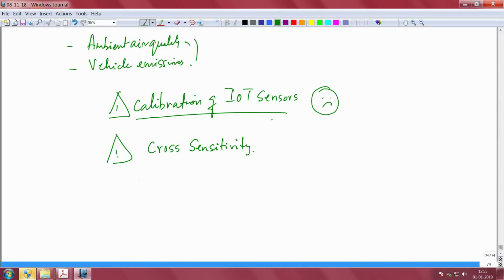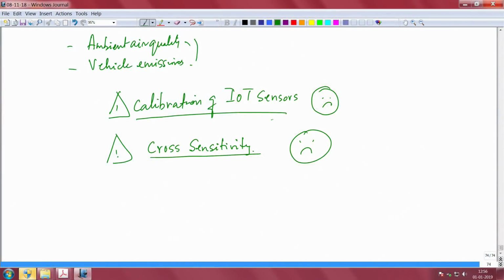If you ask me the problems, one is calibration, the other is cross sensitivity. If you are sensitive to one gas based on an oxidation process, you are also sensitive to another gas which is almost doing the same oxidation process. So cross sensitivity to other gases really is an issue, and we will go into that detail. How do you choose your sensor such that cross sensitivity to other gases is minimized? When it comes to calibration of IoT sensors, this is an issue, and cross sensitivity is also not a nice thing.